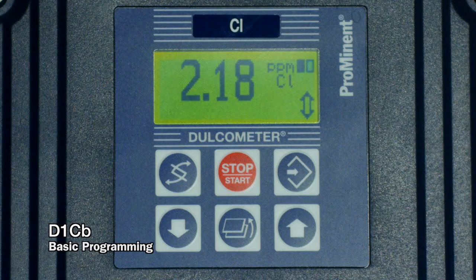Here we're well above 1 part per million. You can see that the dechlor pump would be pumping with the indicating flashing block at the top right. And that's how we set up the basic parameters for an amperometric or a chlorine type sensor on a D1C-B.